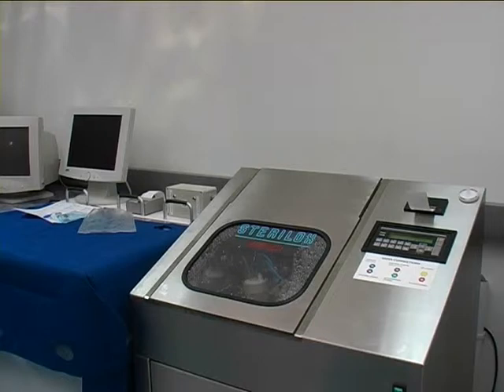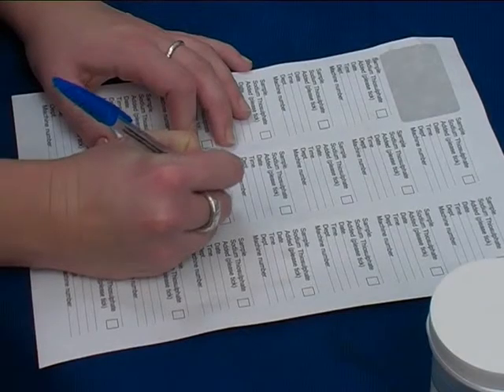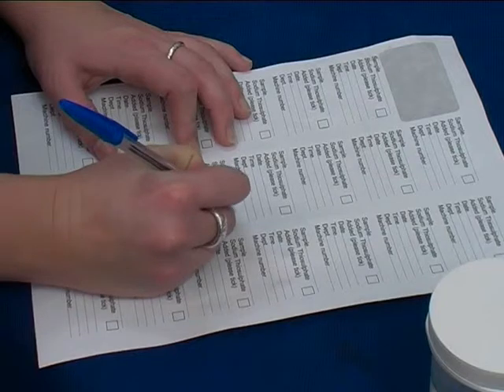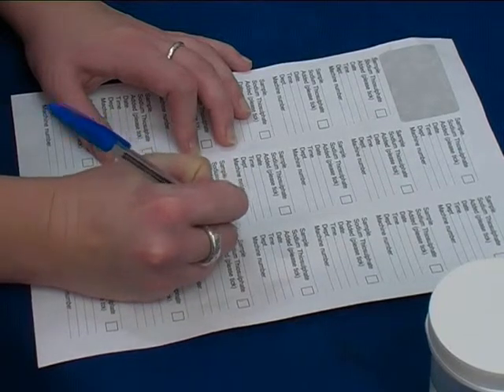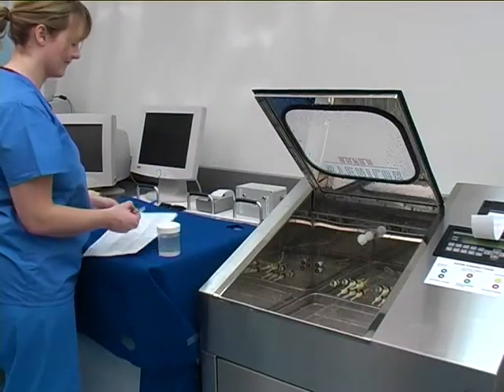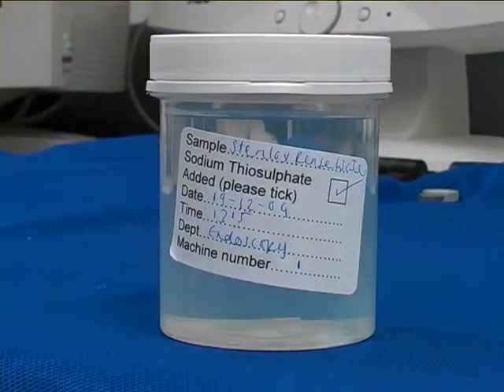The sample collected is approximately 250 milliliters. Send the sample bottle as soon as possible and within a maximum time of 4 hours to the laboratory after labeling with the date, time of sample, identification of sample type, and Sterilox machine identity. Meanwhile, store it at 4 degrees centigrade.